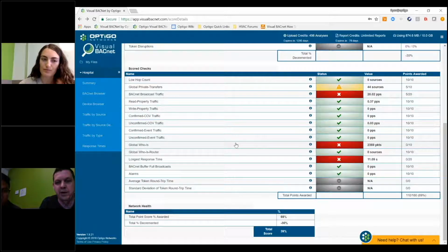I happen to know that the Delta system does go out on a periodic basis to search and make sure the controllers that it knows about are online. That's a lot of this. And you're going to have this twice because I believe the Copper Tree system will do that, and you've got 2 IntelliWeb servers. So all of that's being impacted here in the system.